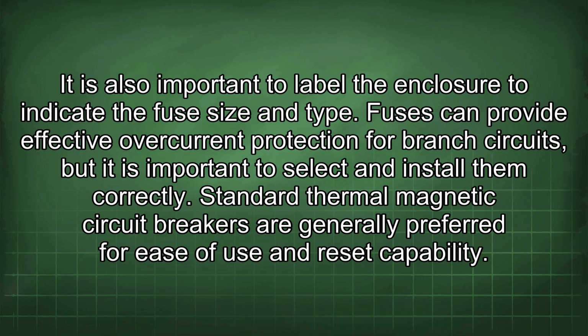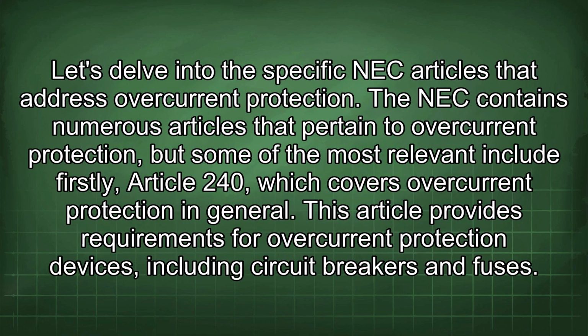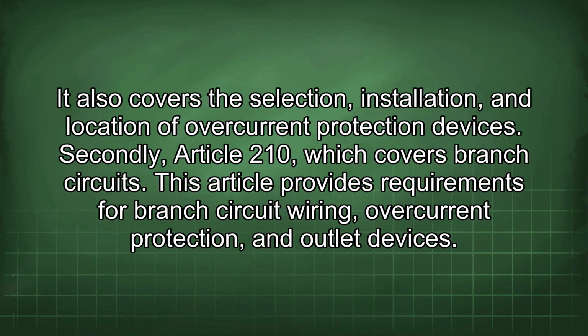Fuses can provide effective overcurrent protection for branch circuits, but it is important to select and install them correctly. Standard thermal magnetic circuit breakers are generally preferred for ease of use and reset capability. Let's delve into the specific NEC articles that address overcurrent protection. The NEC contains numerous articles that pertain to overcurrent protection, but some of the most relevant include firstly Article 240, which covers overcurrent protection in general. This article provides requirements for overcurrent protection devices, including circuit breakers and fuses. It also covers the selection, installation, and location of overcurrent protection devices.